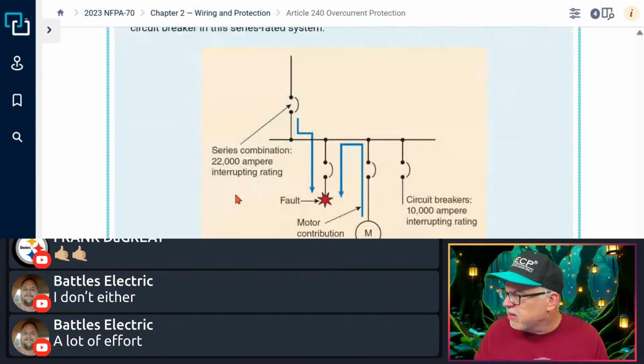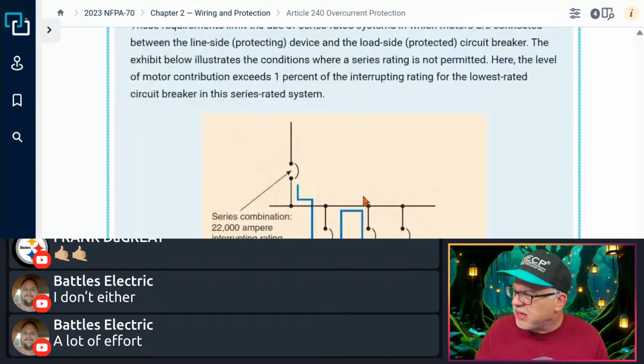Okay, so let's look right here. This is a series rated system. So this is maybe your main breaker, and then it comes down on a bus, and then you have other individual breakers in it, right? Get what I'm saying? So in this case, this right here is 150 amps of motor contribution. Because it's on a motor installed on a series system, the 150 amps is going to exceed the 1% of the interrupting rating of the lowest rated circuit breaker.